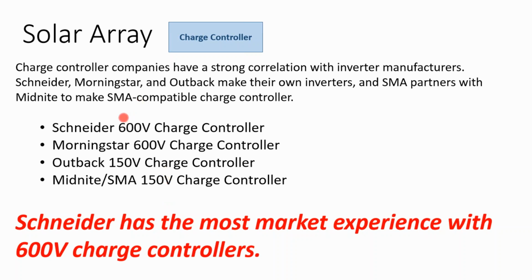And so we went with Schneider because Schneider had both a charge controller and an inverter. We wanted to stay within the same brand name. And then we wanted this 600 volts because it was a rooftop array.